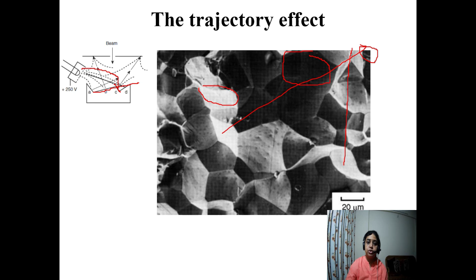Similarly, your detector is somewhere here, that's why this area is brighter. The number of electrons reaching the detector is high in this area. Similarly, over here, over here. However, for the opposite faces, the number of electrons reaching the detector is not enough to create brightness. For an area like this, it is very hard for the secondary electrons to reach the detector. That's why this area looks dark in the image. However, the faces directly facing the detector look brighter like this. So this is the contrast due to the trajectory effect.